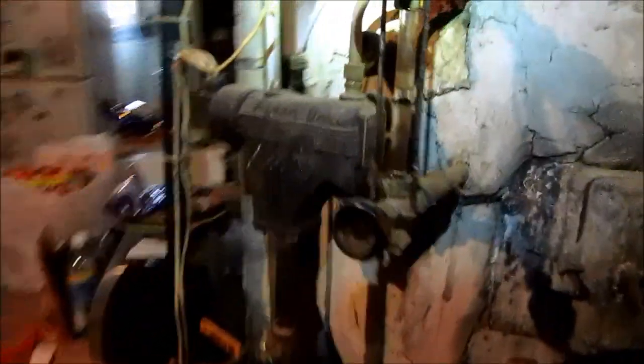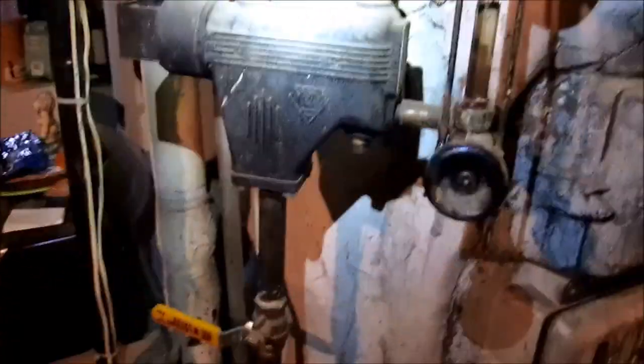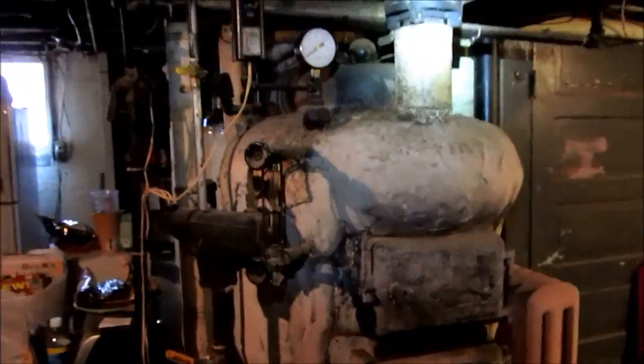I'm looking at the water jacket right now. It's bi-metal — I haven't seen one of those pilots in forever. It looks like we've got water in here. I don't know if my cutoff switch is making it. Let me work on this old beast, see what I can come up with, and do a combustion test on it. First time doing a combustion test on an 1891 boiler.